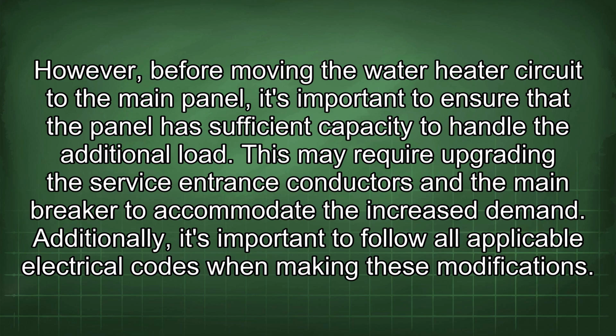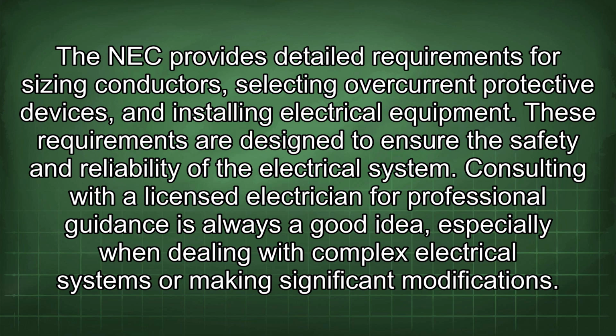This may require upgrading the service entrance conductors and the main breaker to accommodate the increased demand. Additionally, it's important to follow all applicable electrical codes when making these modifications. The NEC provides detailed requirements for sizing conductors, selecting overcurrent protective devices, and installing electrical equipment. These requirements are designed to ensure the safety and reliability of the electrical system.